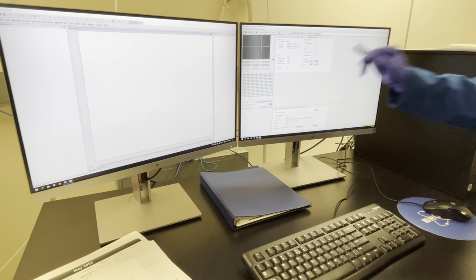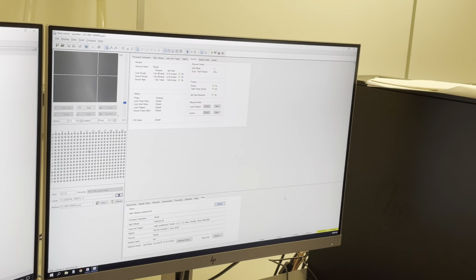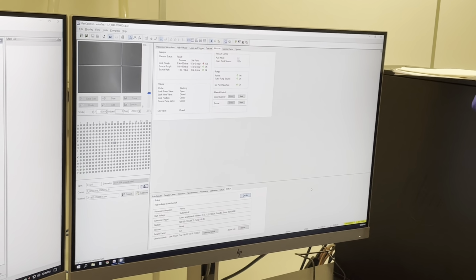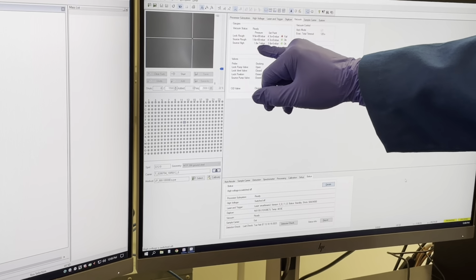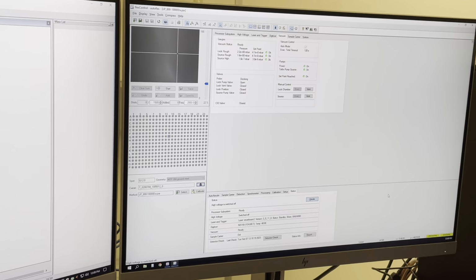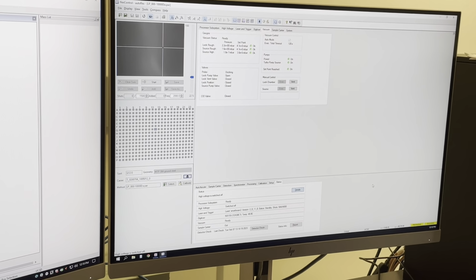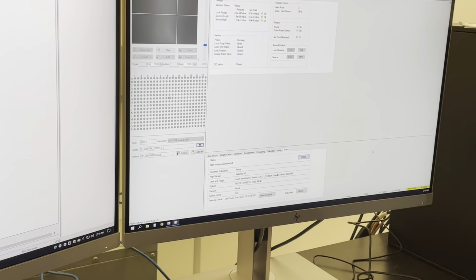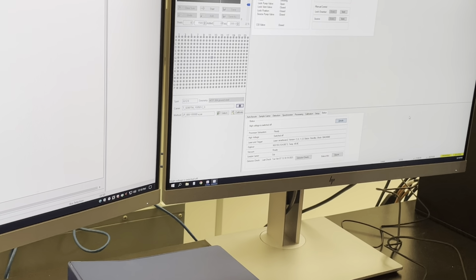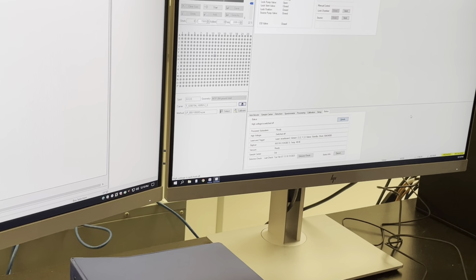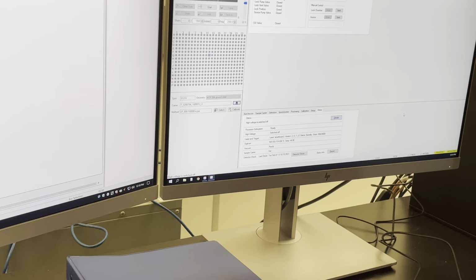So look at here, this is the vacuum reading. This is the important part. Right now, it's loading the plate from atmospheric pressure into the source chamber, which is at a very, very high vacuum, 10 to minus 7 range. And right now, it has a buffer zone. The buffer zone is going to open one door, load the plate into the buffer zone, and then close the other one. And then after that, it's going to load the plate from the buffer zone into the source chamber.